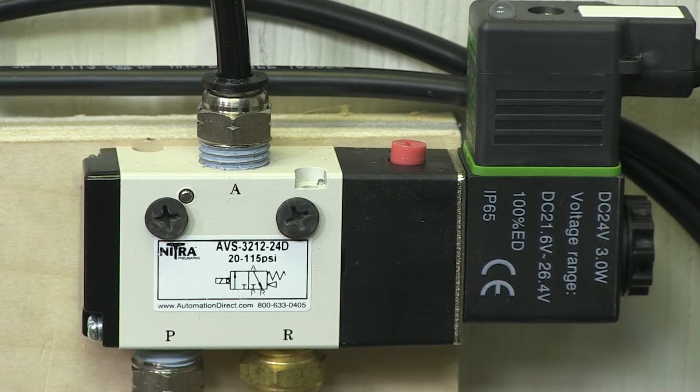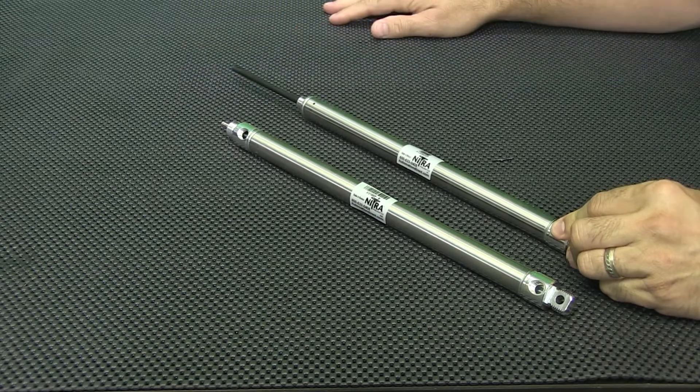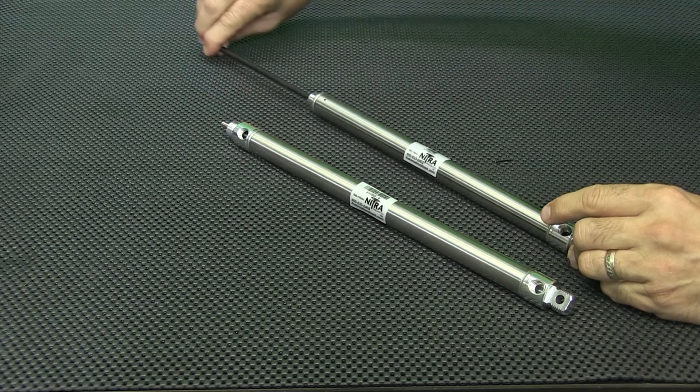When the output turns on, the valve is open, the cylinder extends. When the output turns off, the valve closes, the cylinder pressure is released and the internal spring retracts the cylinder rod.